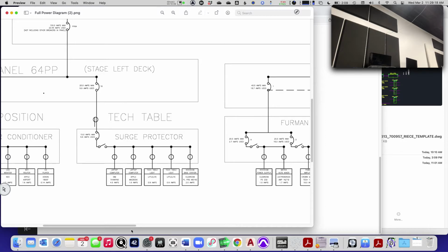That's what you want. And you always want, the further you go down in this, your breakers to be smaller. Like I would never want my surge protector to have a 20 amp breaking capacity, but my panel to have a 15 amp. Because then I could be doing something here, and the breaker here would not trip, but the one up here would, and it would take out everybody else. Right? So you don't want that.